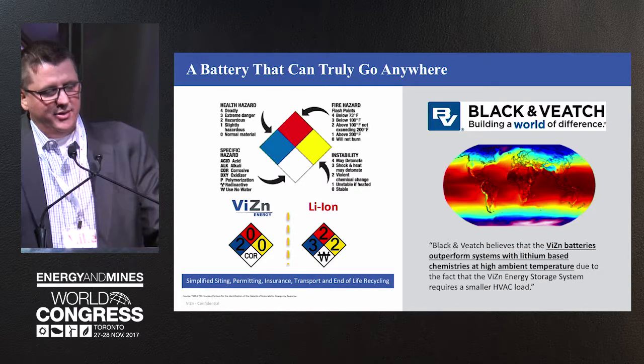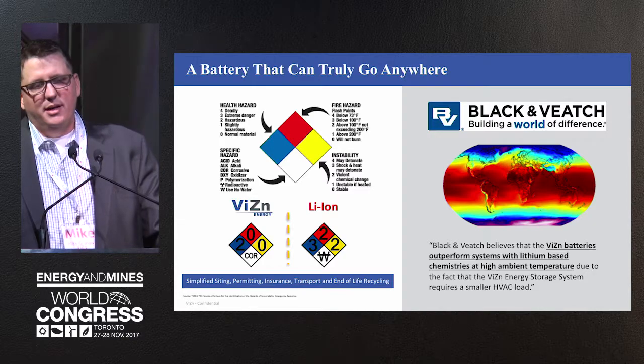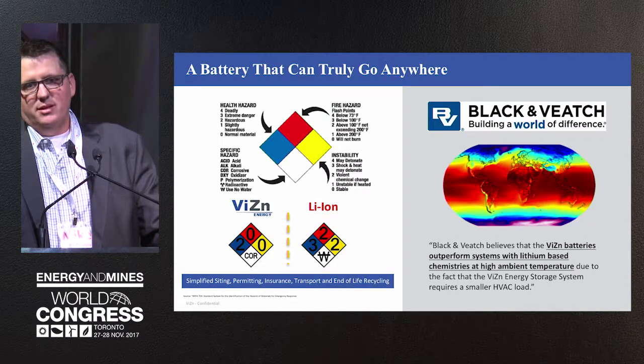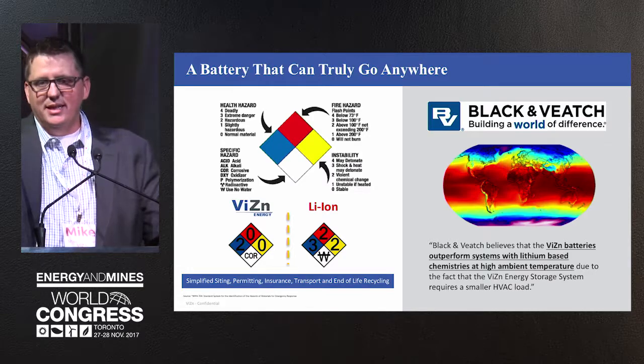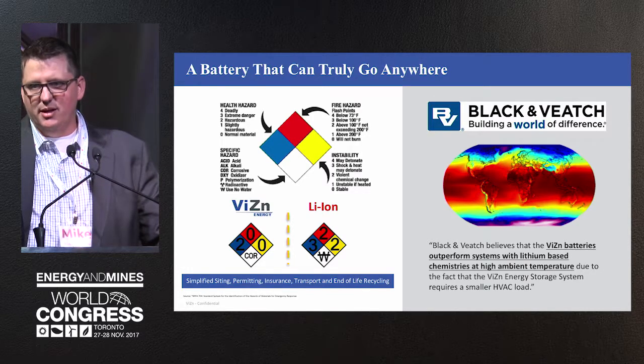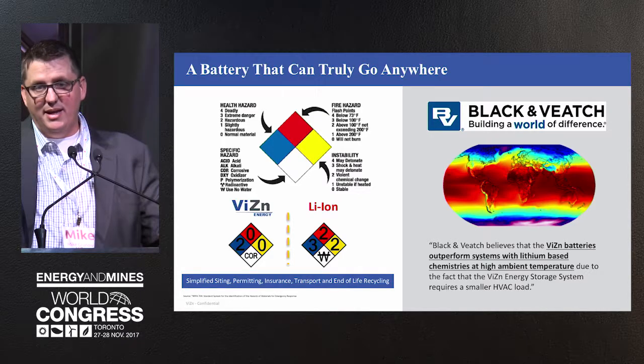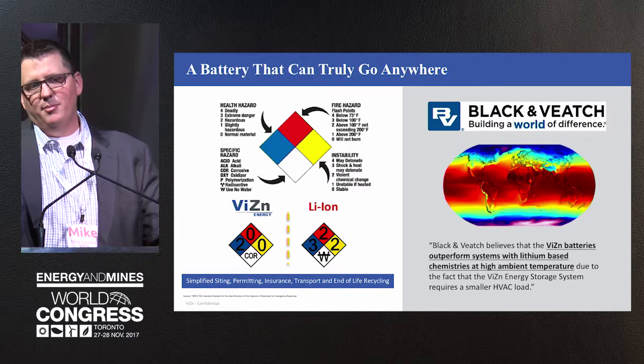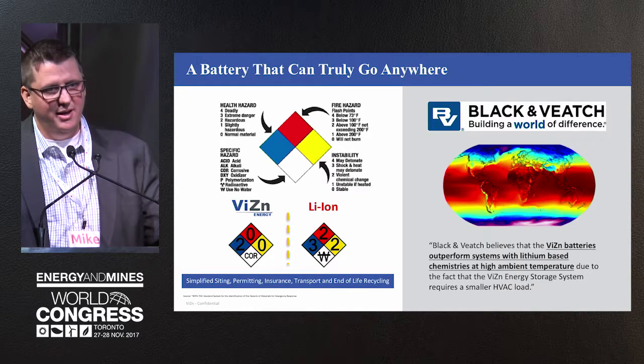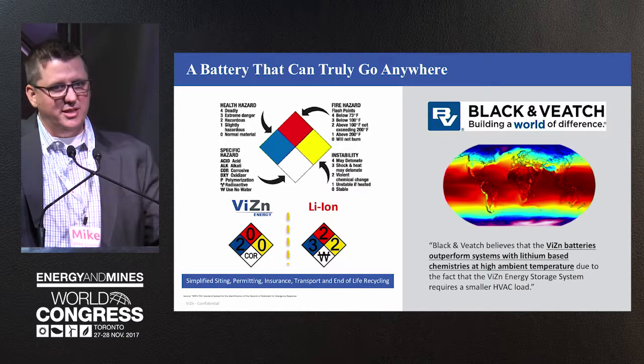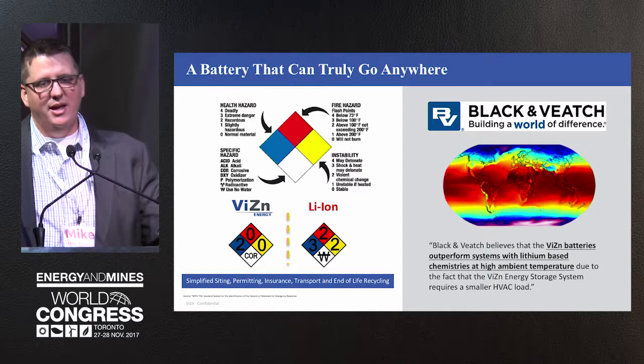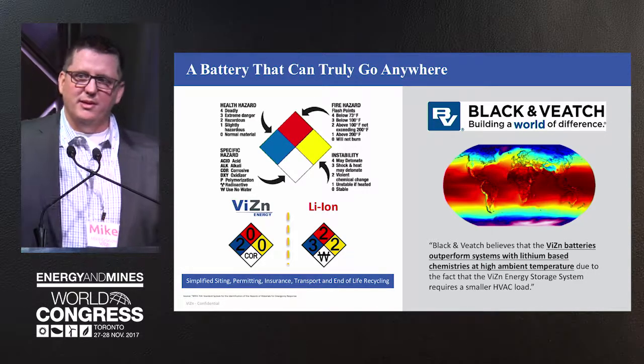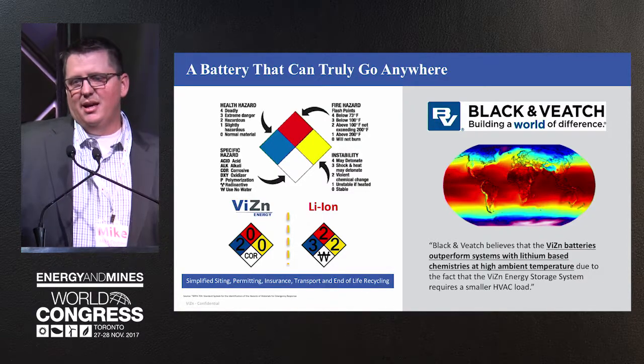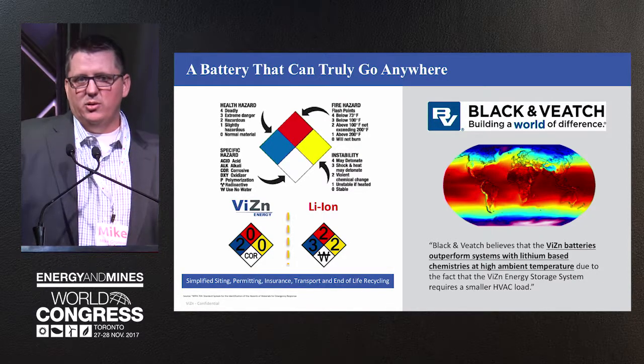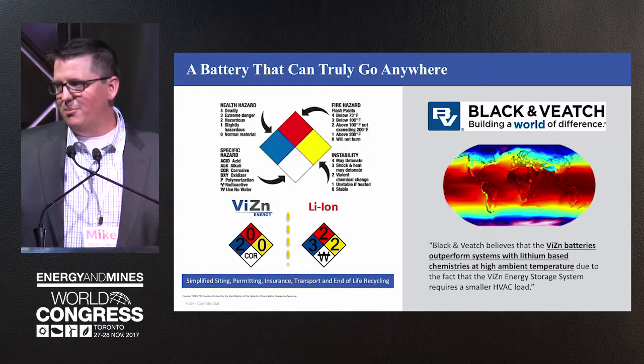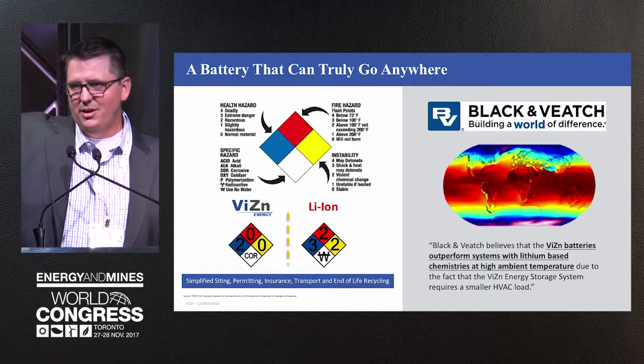On the right is another key point. Anybody who's seen a large lithium ion battery installation knows it has a massive HVAC - heating, ventilating, and air conditioning supply handler - to maintain the internal temperature between 70 and 75 degrees Fahrenheit. Outside that window, you see accelerated decay in a lithium ion battery. What's not talked about when vendors discuss round trip efficiency is the auxiliary load of constantly running HVAC to keep batteries within these ideal temperature windows.